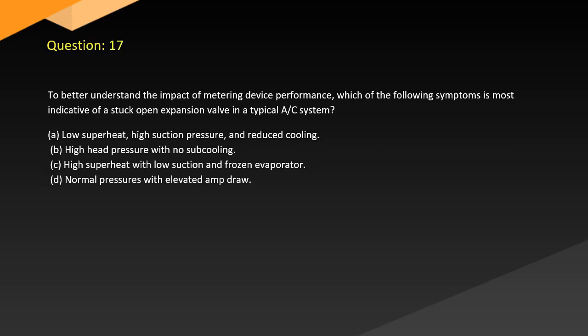Question 17. To better understand the impact of metering device performance, which of the following symptoms is most indicative of a stuck-open expansion valve in a typical AC system? A. Low superheat, high suction pressure, and reduced cooling. B. High head pressure with no subcooling. C. High superheat with low suction and frozen evaporator. D. Normal pressures with elevated amp draw.